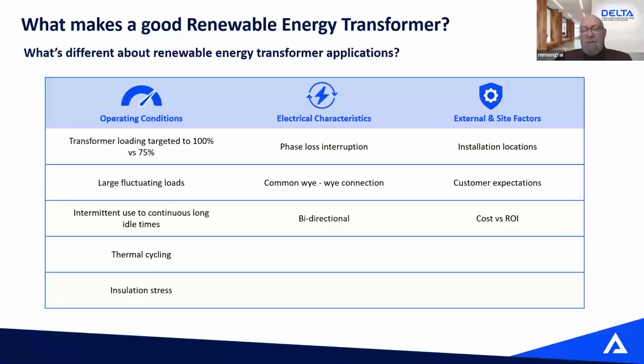What is also very different about renewable energy transformers is that they are the center of a system. They don't just take feed from the grid on the primary and supply load on the secondary, in one direction. They have to be bi-directional, so they can take the energy from the inverter and push it into the building. Or if there's a battery storage system, they can recharge the battery from the energy from the building or the generating system. So that's also different.